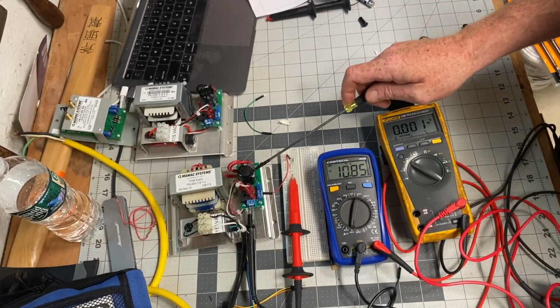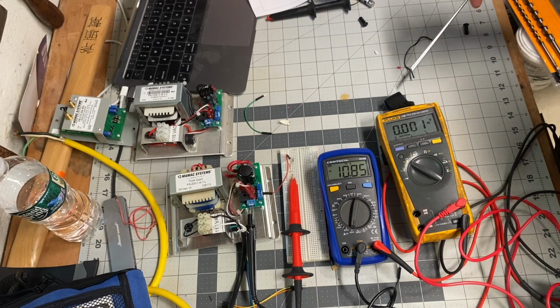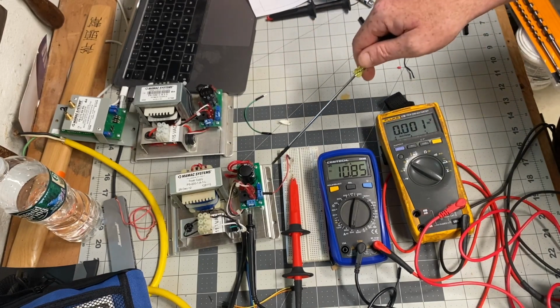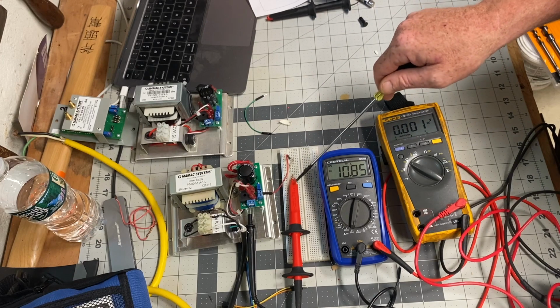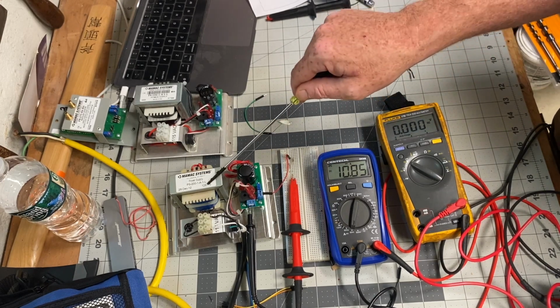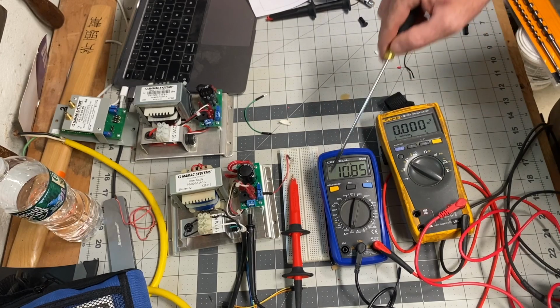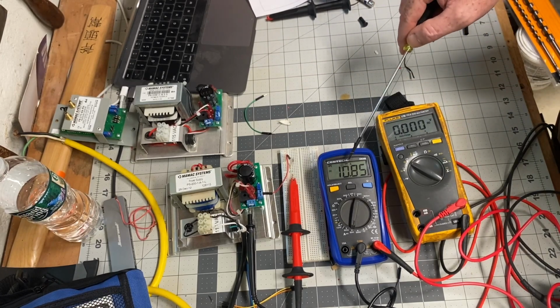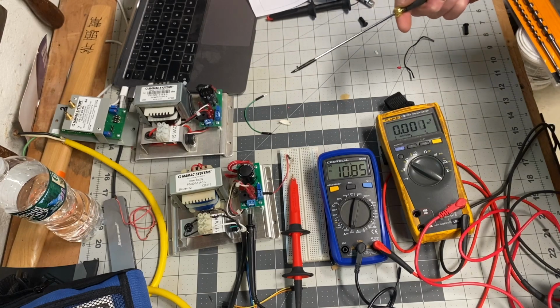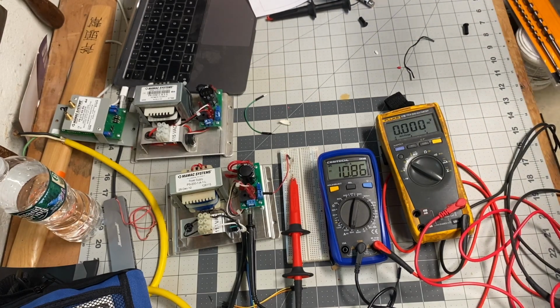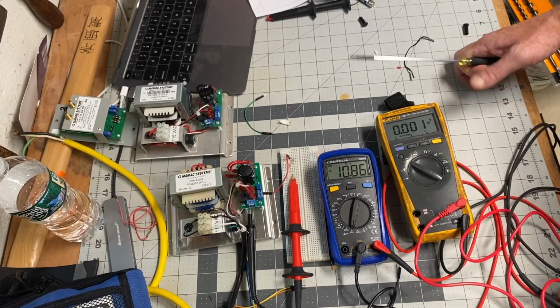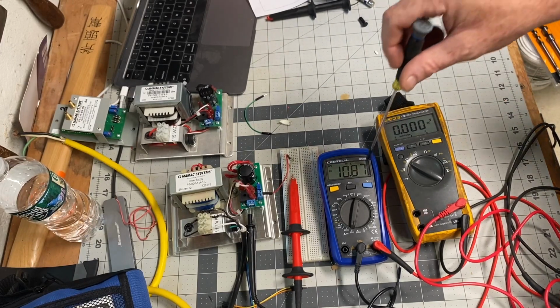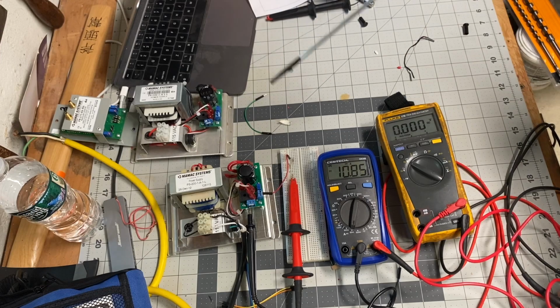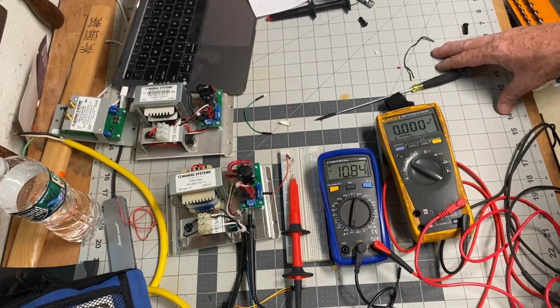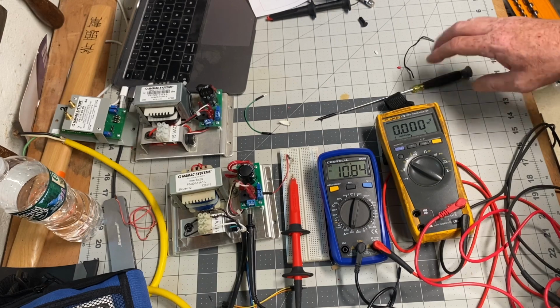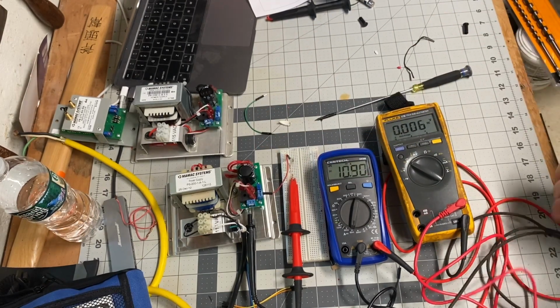So I'm pretty sure that capacitor blew out. Now, what would happen is if this is connected to the building automation system and we've got a known value here, 2000 ohms, 24 volts DC, you should be getting the 12 milliamps. I would take this reading and set it up as an alarm, right? So anything below, let's say 11 or 11 and a half milliamps, it would give us an alarm into the system to tell us we have a bad power supply. Like I said, this was reading 19 when we found it.